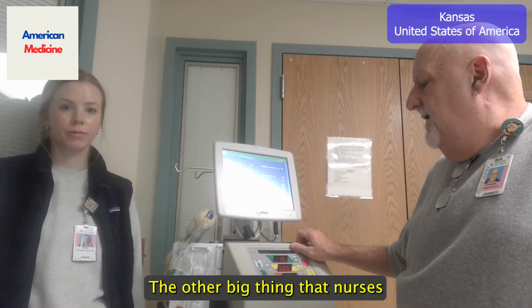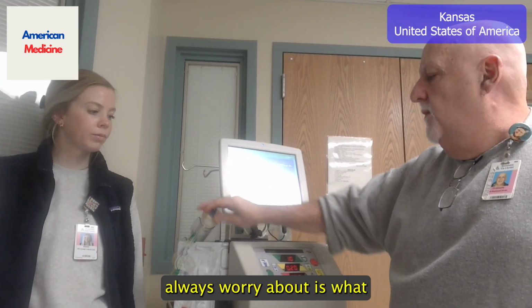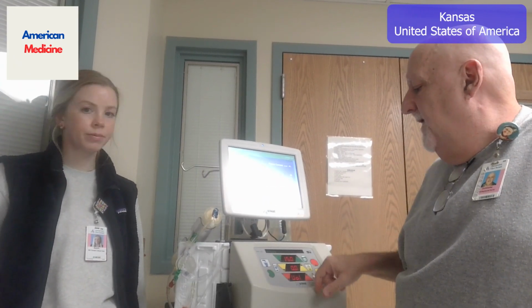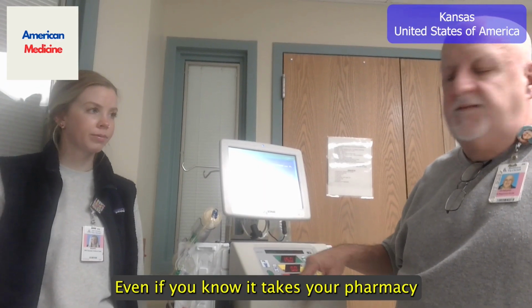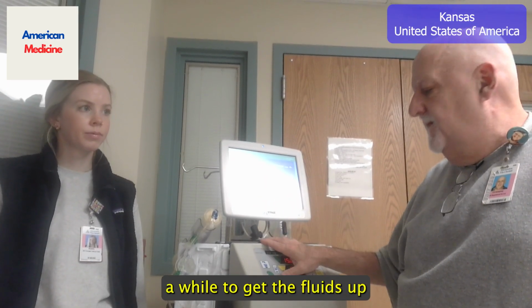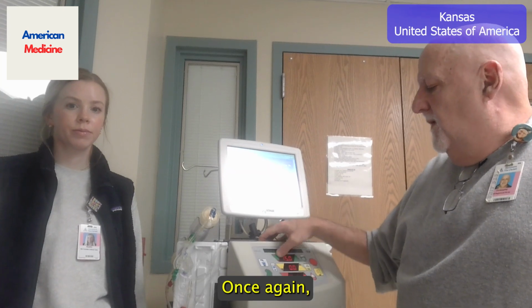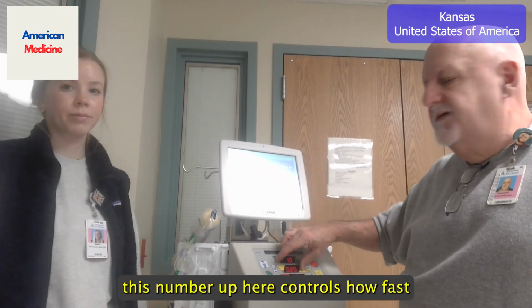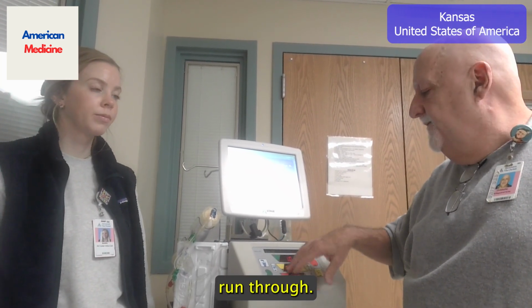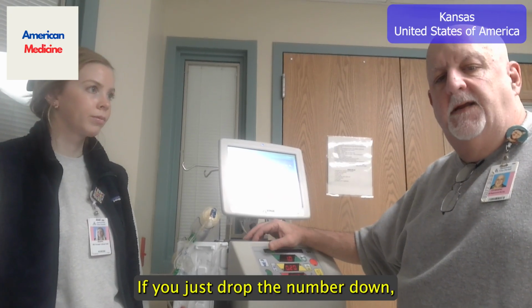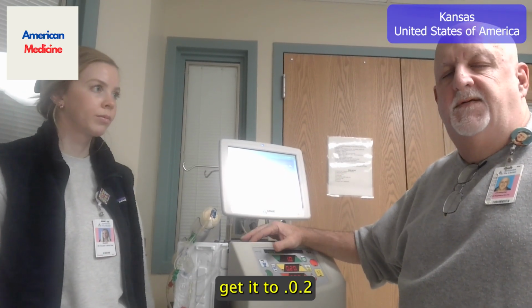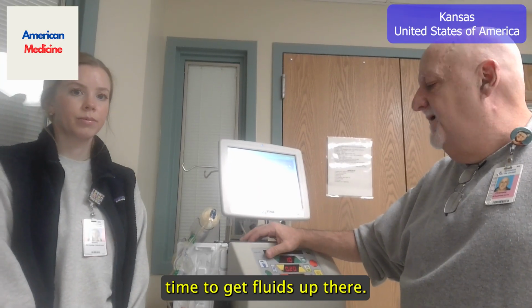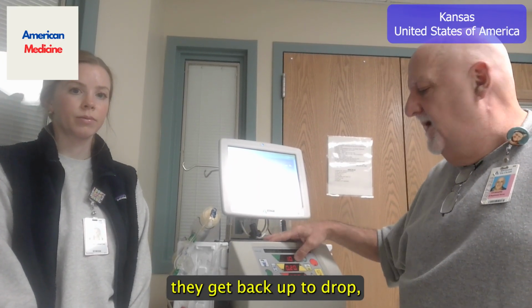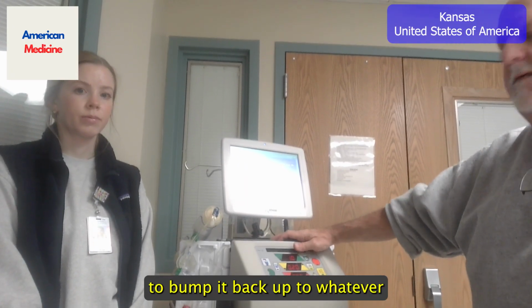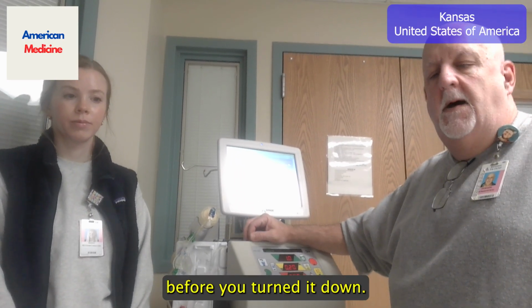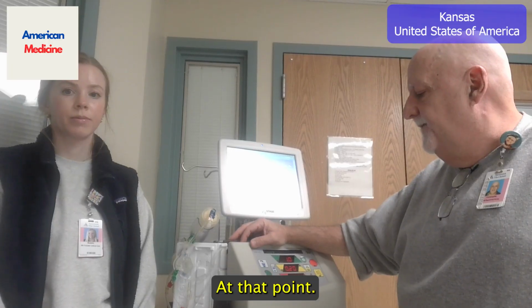The other big thing that nurses always worry about is what to set their volume for. Even if you know it takes your pharmacy a while to get the fluids up, or get the dialysate up to you, once again, this number up here controls how fast it runs through. If you just drop the number down to 0.2, that will buy you enough time to get fluids up there. Just remember, once they get back up, to bump it back up to whatever your dialysate was running before you turned it down.